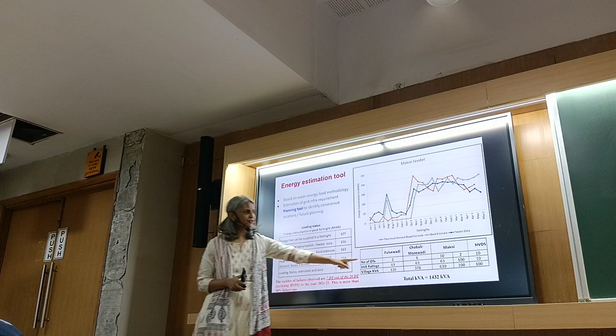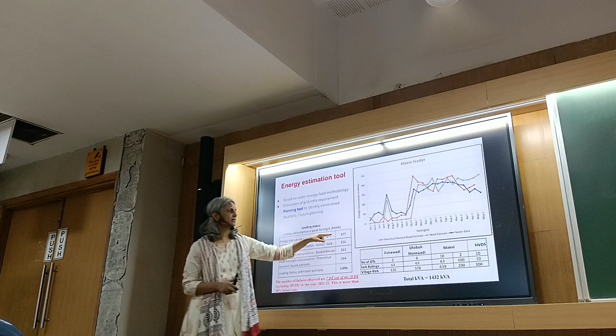Now how much is the demand here? According to our model, you need 163 megawatt hours to be supplied in that peak fortnight. The data shows 156, which is not so different. But this infrastructure capacity, the DTs in these 4 villages on this feeder, has a total KVA rating of about 1400 kVA, and that can only supply 127 megawatt hours. That means it's an overloading of 130%.